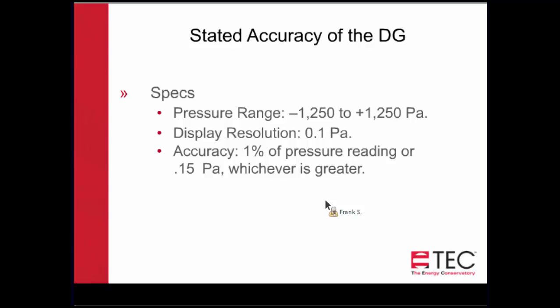The specs of the DG700 are that we have a pressure range of 1250 pascals, both negative and positive. So when you're doing a pressurization or depressurization, the range has a maximum of 1250 in either direction, and has a display resolution of 0.1. The accuracy statement for our DG700 is 1% of pressure reading or 0.15 pascals. So as a standard, our instrument will easily meet and exceed the BPI requirements.